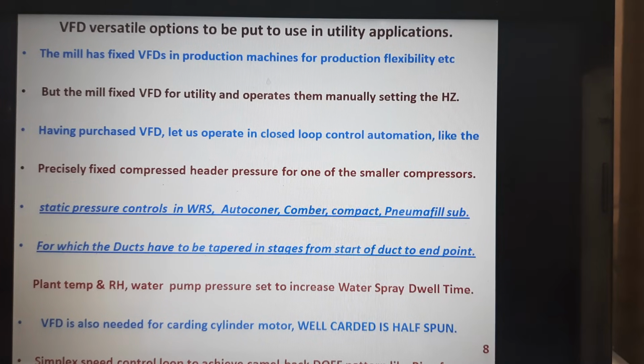But on the utility side, we find the VFDs are fixed. They are only operated manually, only on hertz. This is not at all enough for us. This needs to be on closed loop control. The automation needs to be there when the VFD is there, and if this automation is done on the VFD on any of the process parameters inside the mill, on the utility parameters, it will give excellent energy savings. You make the utility parameters precisely fixed, with no variation in them, and definitely this will give enormous savings to the textile mills.